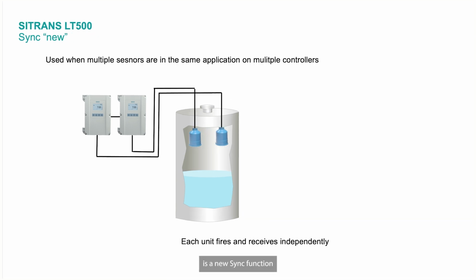There's a new sync function in the SITRANS LT500 where we can provide multiple sensors in the same application on multiple controllers. So typically we only get requests for these in very critical applications where sensor and controller redundancy are required. And this is where you would have two independent sensors and controllers. So different than a dual point device, we actually have two completely independent systems.